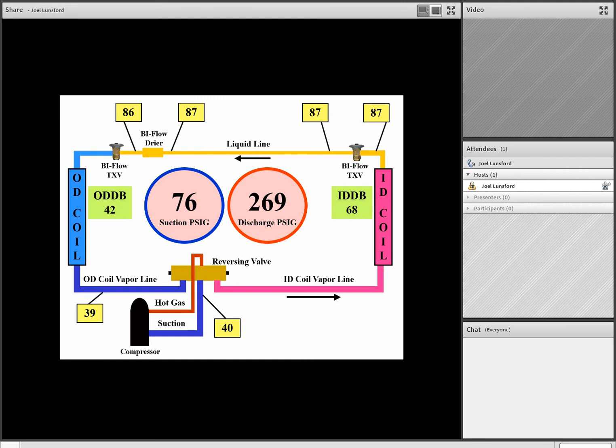The temperature leaving on the cool or the cold outdoor coil is 39. So we have a 21 degree superheat on the outdoor coil. So let's keep working at 269 pounds of pressure on the discharge line for 410A. At 269 pounds of pressure, we have about a 89 degree pressure temperature conversion, and we have 87 degrees leaving the warm indoor coil. So let's convert that. We see that our subcooling is very, very low on the indoor coil.